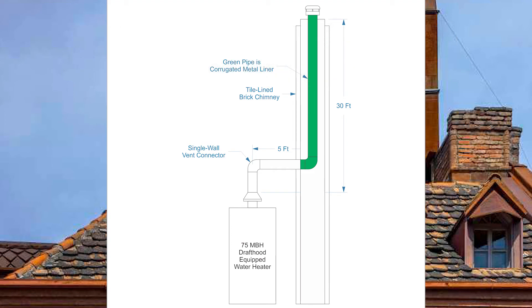Since 4 inch is not sufficient after derating, we go up one size. The final size of the vent and vent connector will be 5 inch. That brings us to the end of this video series — you've made it! Have yourself a great day.